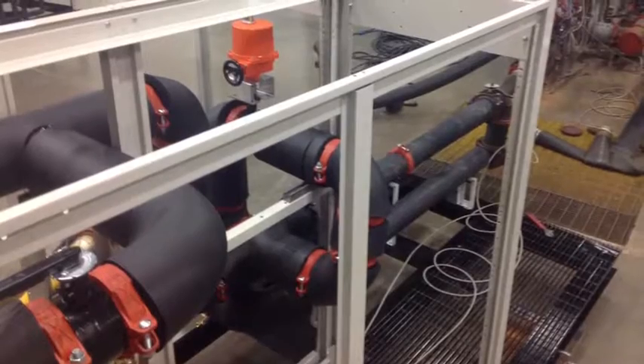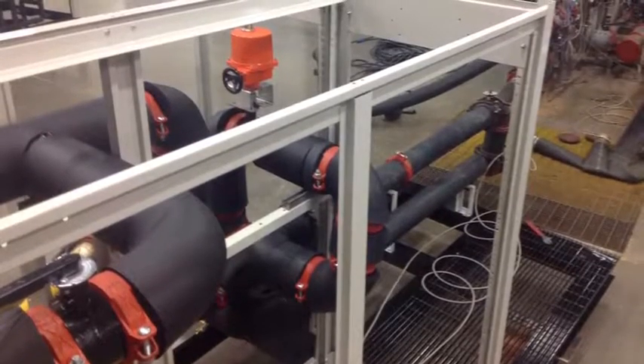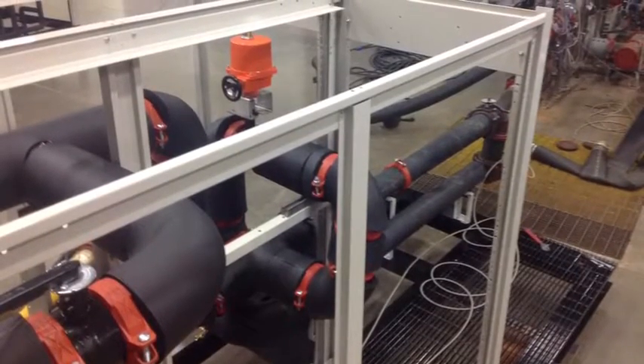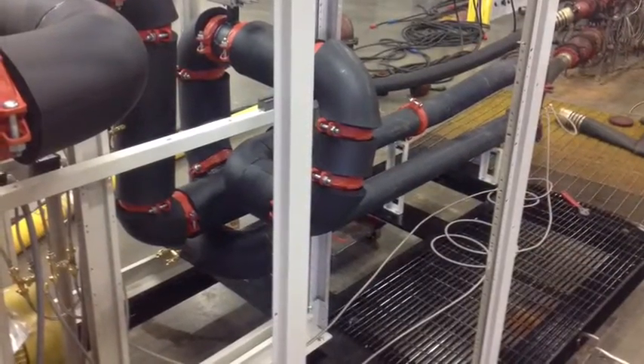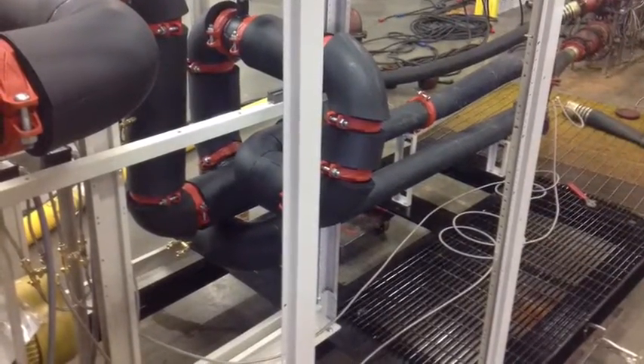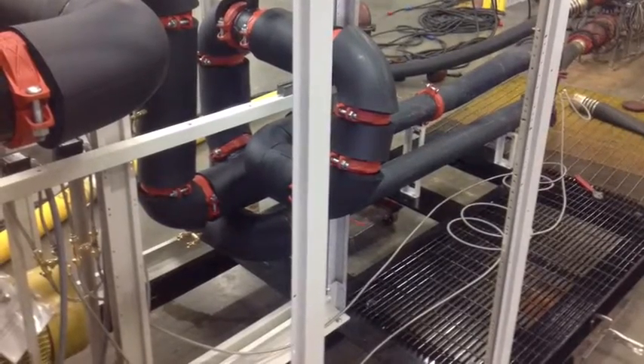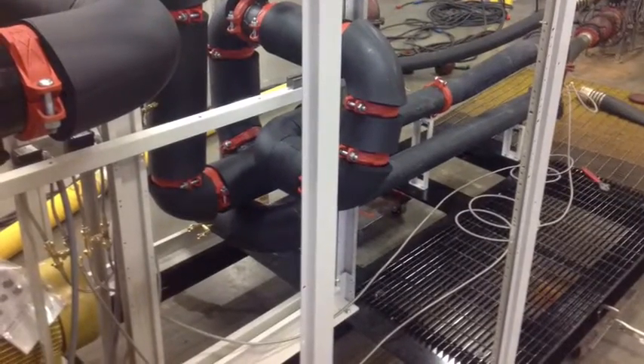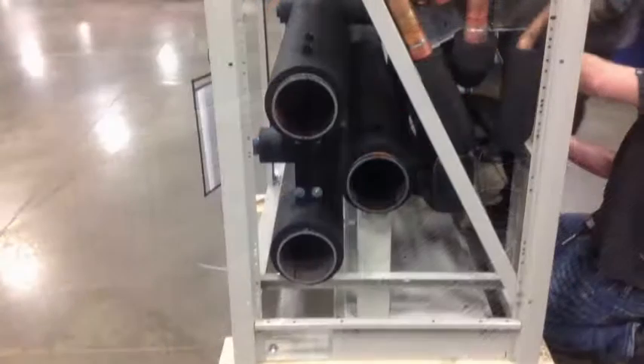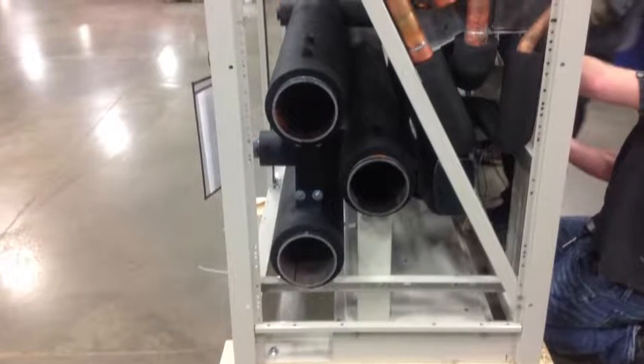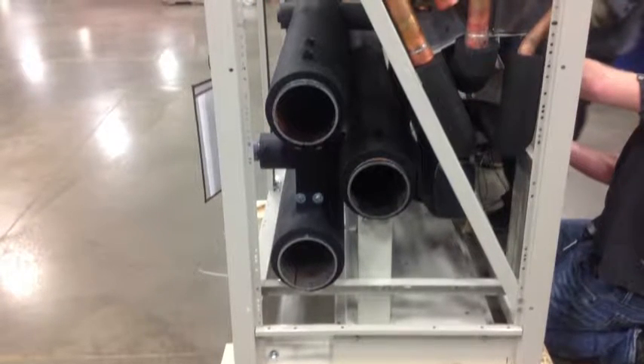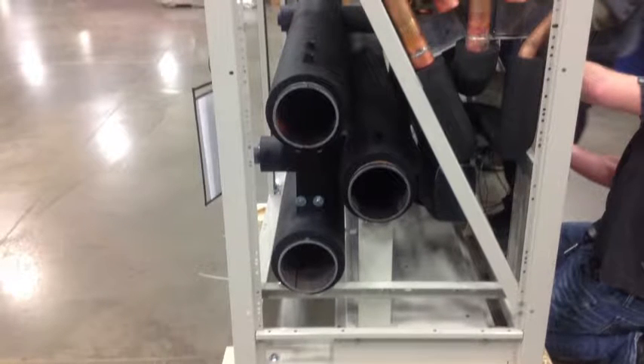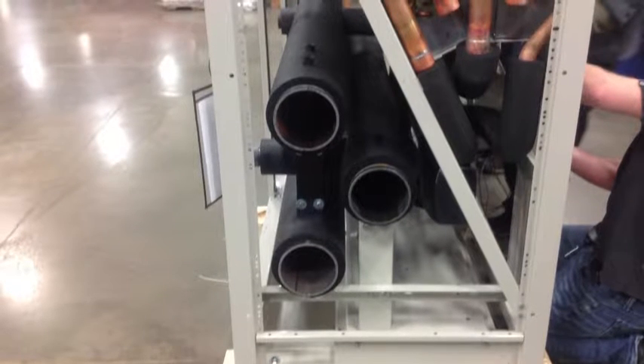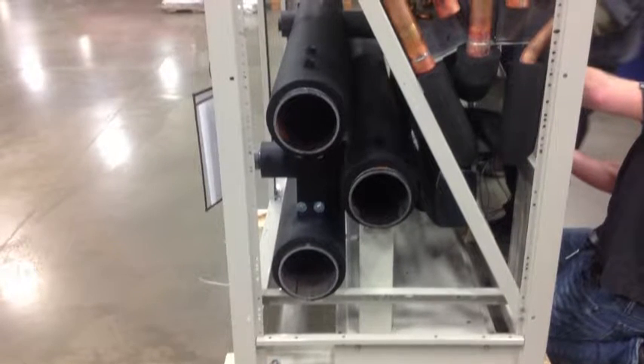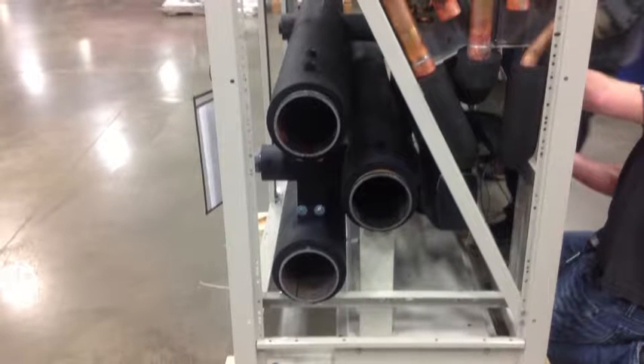From the top view we can see the Belimo actuator on the free cool bypass valve. This is installed for the future installation of free cooling modules in the currently open array, downstream of the pumps. This is the view of a standard free cooling module. A tour of this free cooling module will help you understand the piping configuration in the future free cool section between the pumps and the first mechanical array.